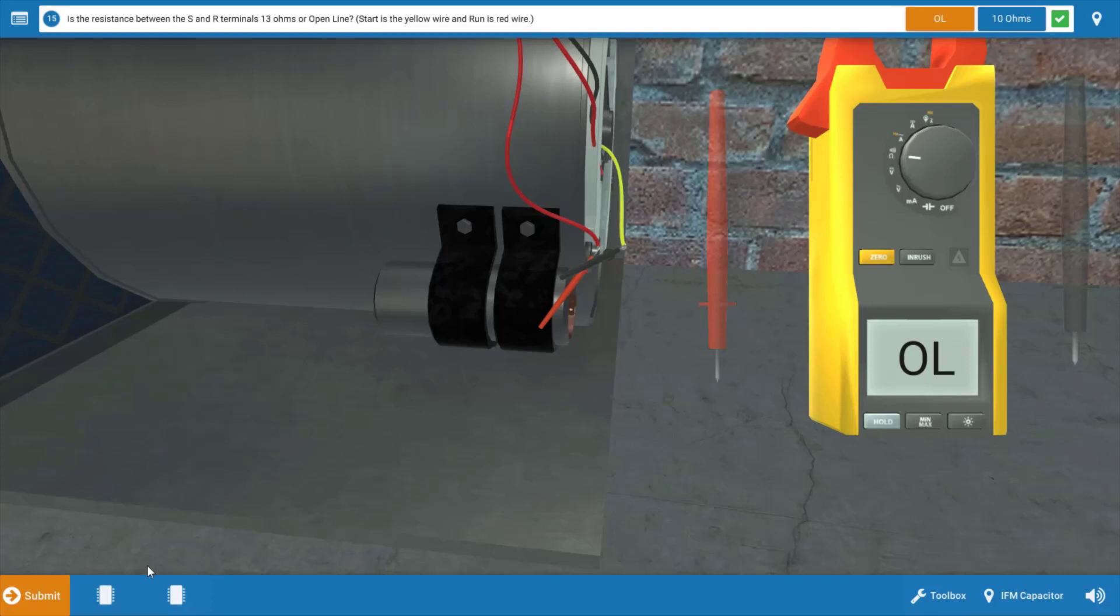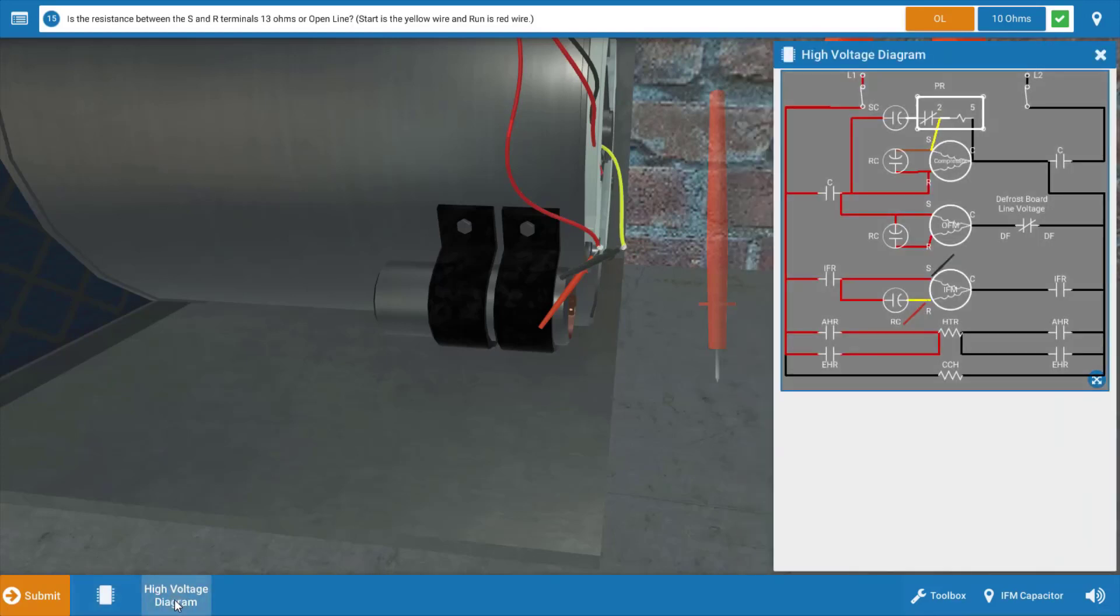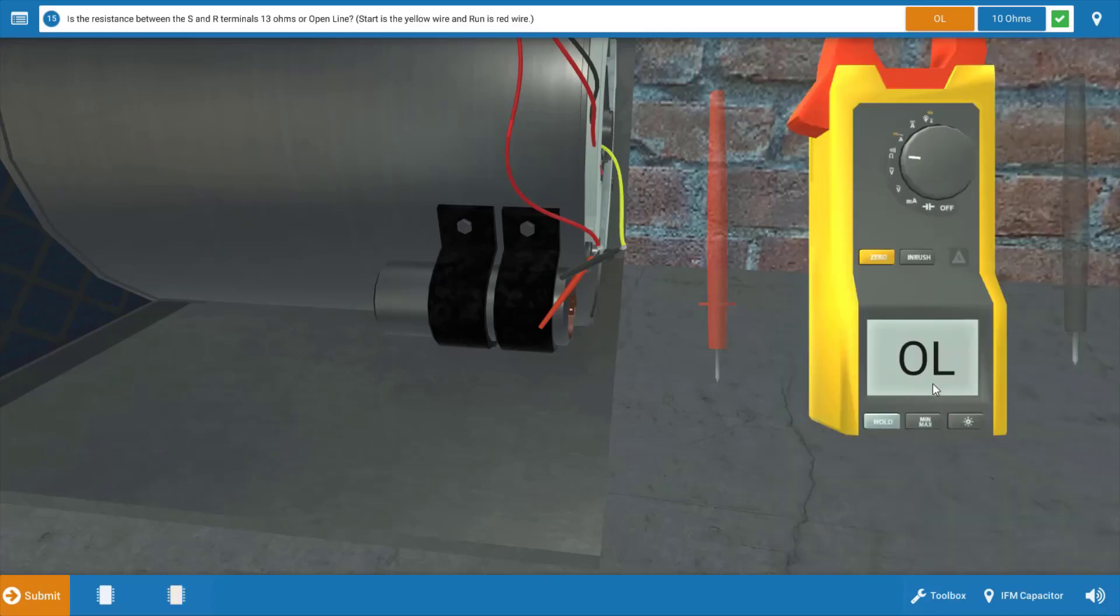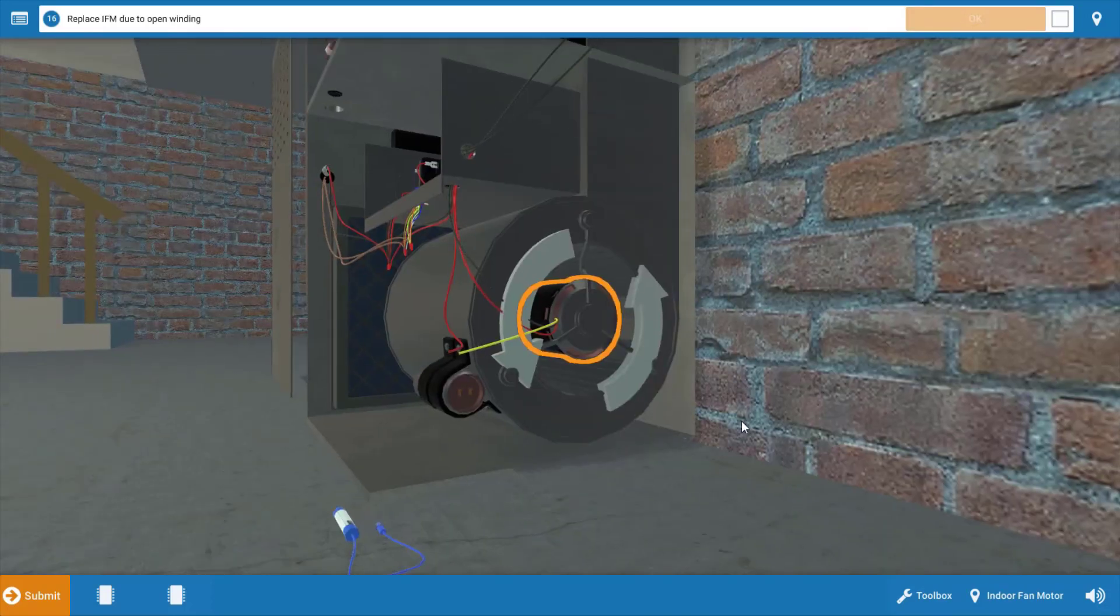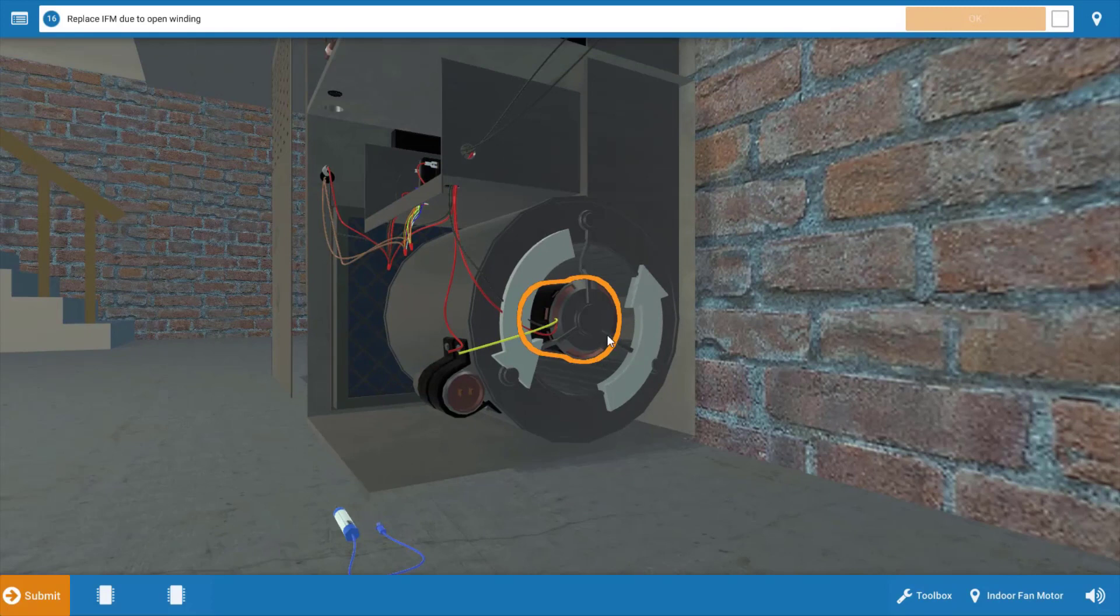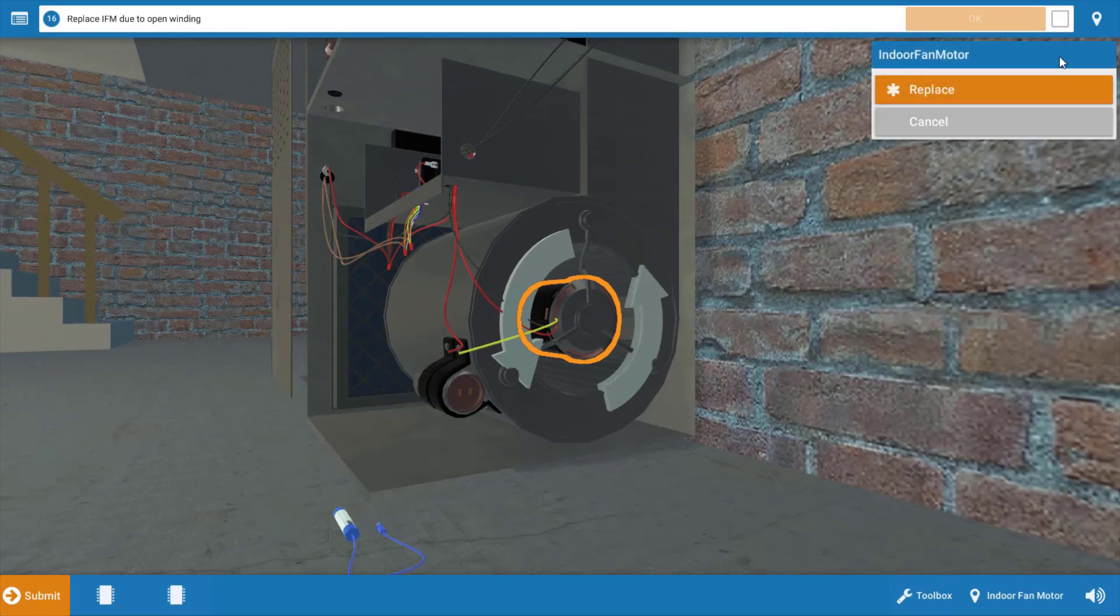If you're a little confused on this, let me show you on the wiring diagram. We're going to take out the line voltage wiring diagram. We can see our meter leads are placed across run and start, which measures resistance across both of these windings. When we do this, we see we have an open circuit here. OL indicates infinite resistance, which means that one of these windings is open. Now, if you want to find out which one, you can check them individually, but that's not really necessary because we're going to need to replace the motor regardless. So we're going to click OL or infinite resistance on the procedure guide.